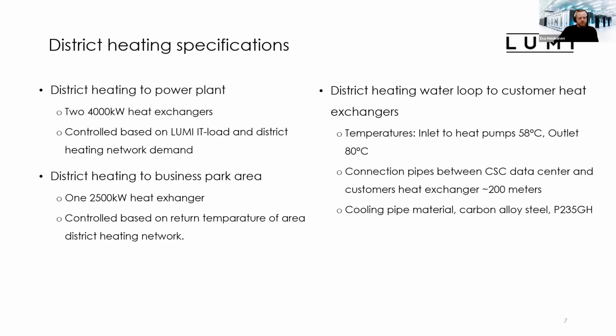So then about district heating specifications. The district heating power plant is providing district heating for the city of Kajaani. We have two 4 megawatt heat exchangers, so we can provide a total of 8 megawatts of district heating for the city of Kajaani. This is controlled based on the Lumi's IT load and district heating network demand. And then we are also providing district heating for this business park area. There is currently one 2.5 megawatt heat exchanger installed, and this is controlled based on the return temperature of the area district heating network. So if it gets too high, we know that there is not enough demand, and we start to restrict the flow to the area district heating.